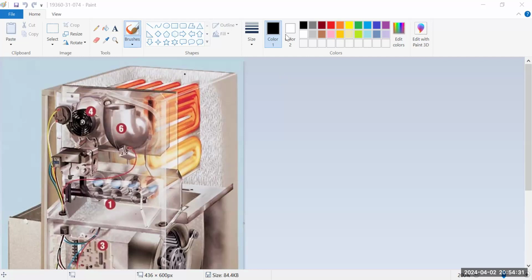So any old furnace, you got to check the heat exchanger. If you don't check it, who's going to? That's the way I always looked at it. If they have a 20-year-old furnace, I better look at the heat exchanger, because if I don't look at it, no one's going to look at it. It's not like the cable guy is going to be like, oh, hey, let me check out your heat exchanger. No one's even thinking to look at it other than an HVAC tech.